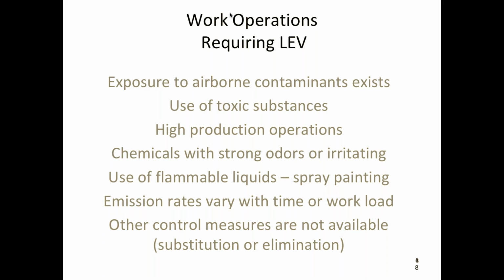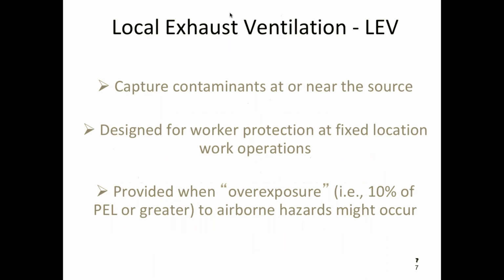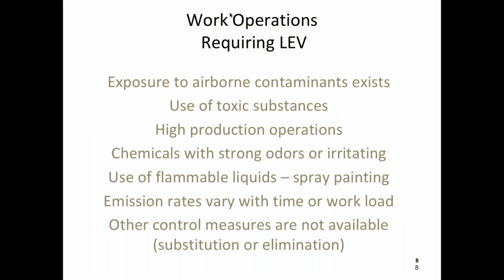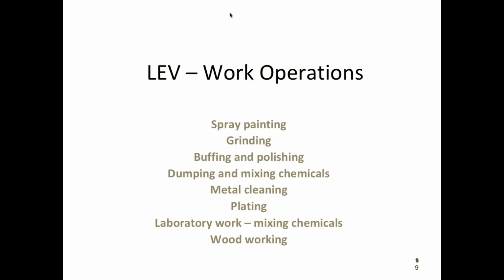Okay, good. Okay, where do you use it? So local exhaust ventilation is usually used in situations where you have a bigger hazard. A lot of times you'll get away with dilution ventilation because the hazard is relatively low. But if you have something that's a real hazard, then you want to make sure that you capture it as efficiently as possible. You don't want the worker exposed to it at all. Toxic substance, high production operation, chemicals with strong odors or irritating, flammable liquids like spray painting. They have spray booths where they do spray painting, and so on and so forth.